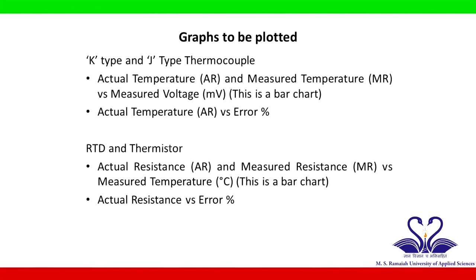In this experiment, we need to plot two graphs, each for K-type, J-type thermocouples, RTD and thermistor. The first graph to be plotted for the thermocouples is a bar chart or histogram depicting the actual and measured values of the temperature against the measured voltage. For the RTD and thermistor, the histogram to be plotted is the actual and measured values of resistance against the measured temperature. The second graph is a line graph depicting the actual temperature versus error percentage for the thermocouples and actual resistance versus error percentage for RTD and thermistor.